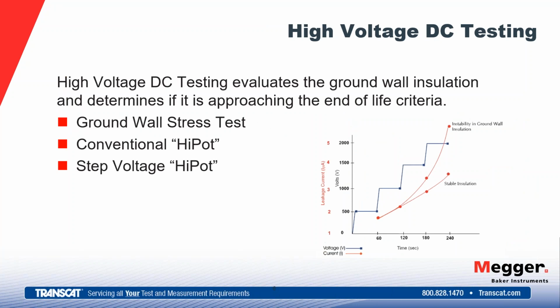After doing the low voltage insulation resistance testing, we're going to raise that voltage up and evaluate the ground wall insulation. This helps us determine if it's approaching the end of life. So again, we're applying voltage here. We're going to read our current. We're stressing that ground wall insulation because that's where our differential is.